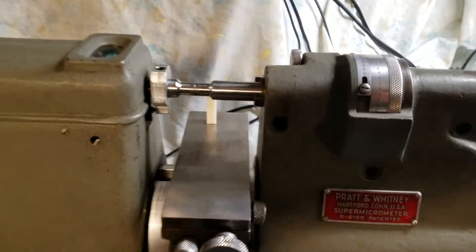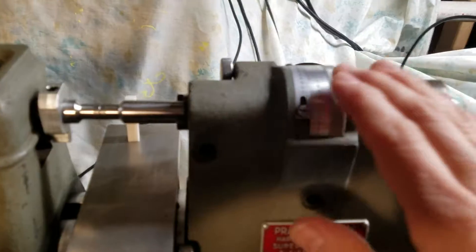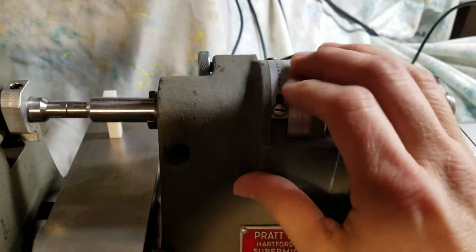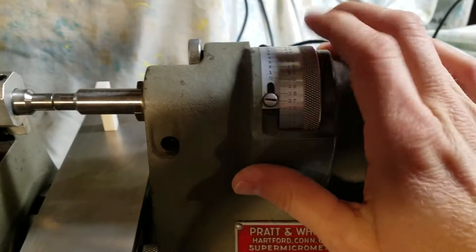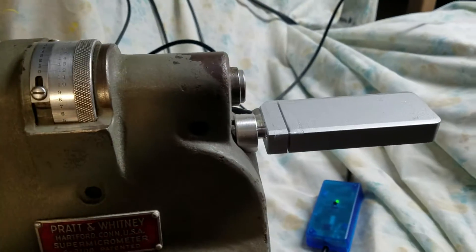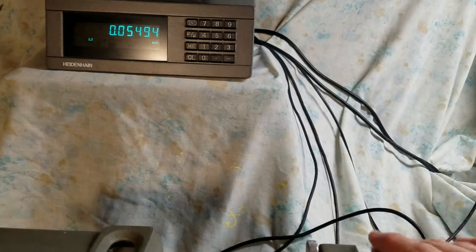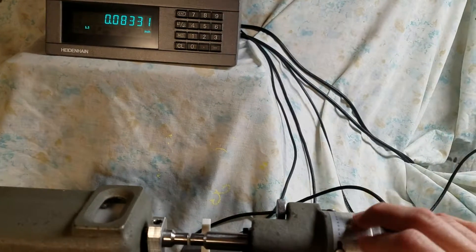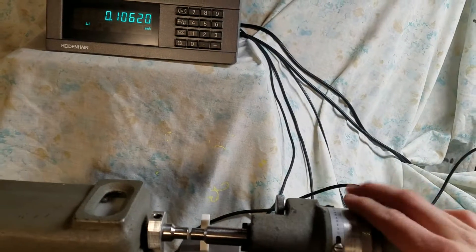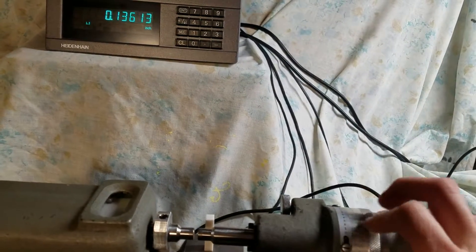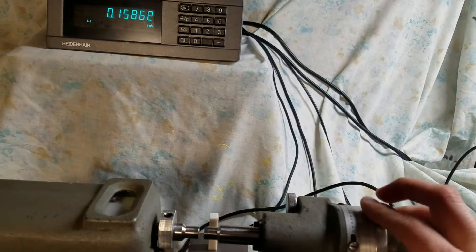The one-inch micrometer wheel has been adapted with a high accuracy glass scale probe. This allows you to master and measure up to one inch away from your master. The linearity has been checked and is within 20 millionths.